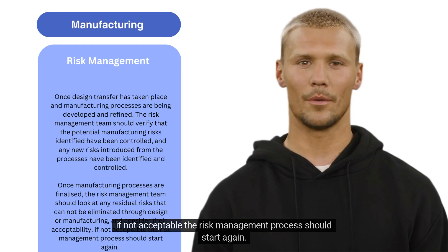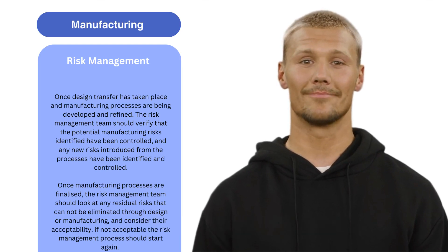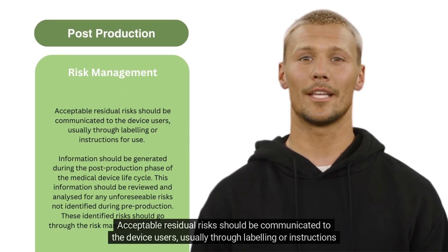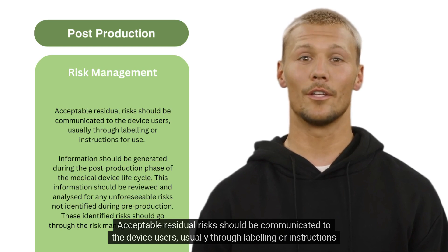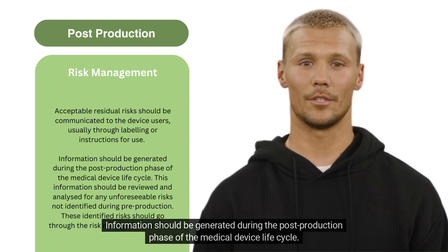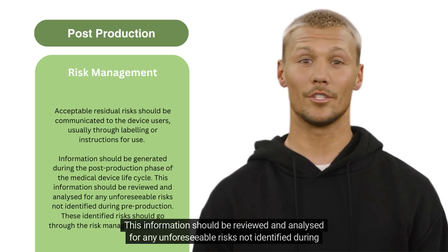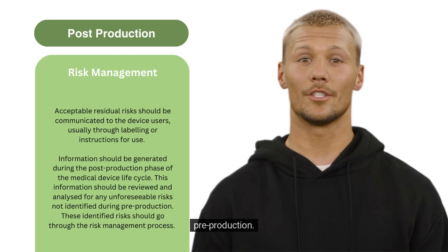If not acceptable, the risk management process should start again. Acceptable residual risks should be communicated to the device users, usually through labeling or instructions for use. Information should be generated during the post-production phase of the medical device life cycle. This information should be reviewed and analyzed for any unforeseeable risks not identified during pre-production.